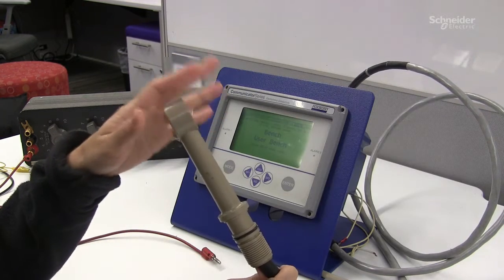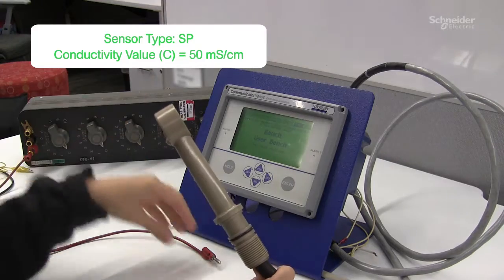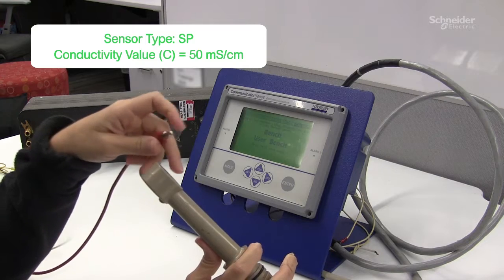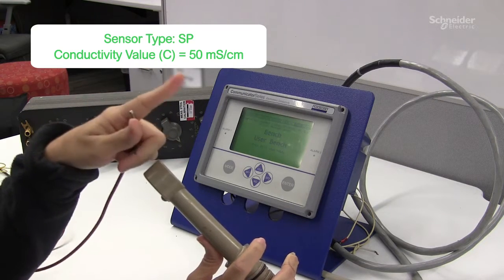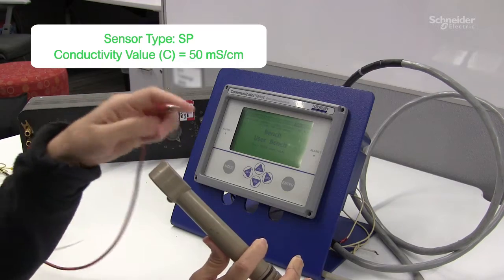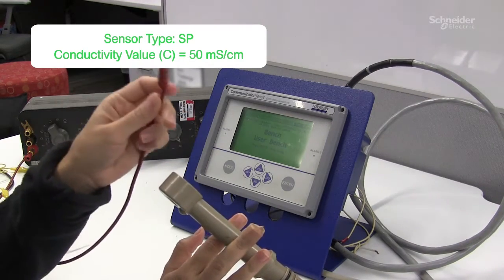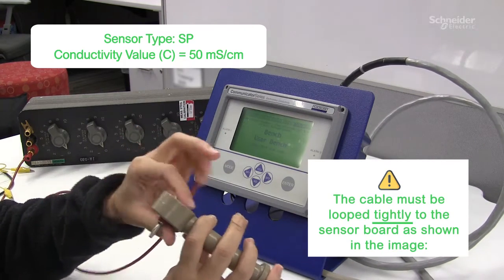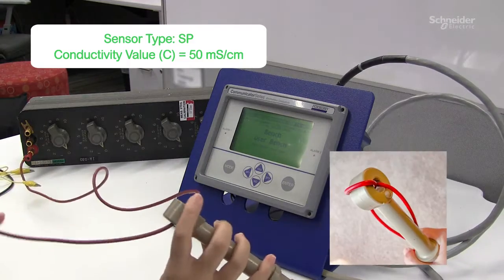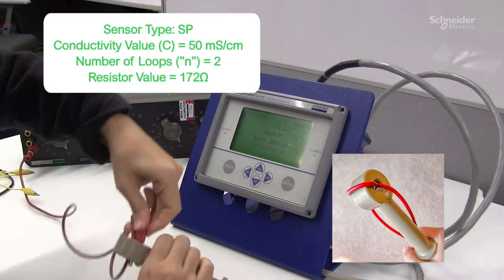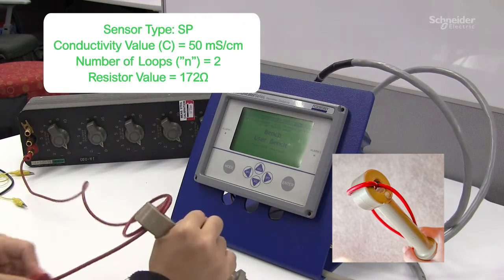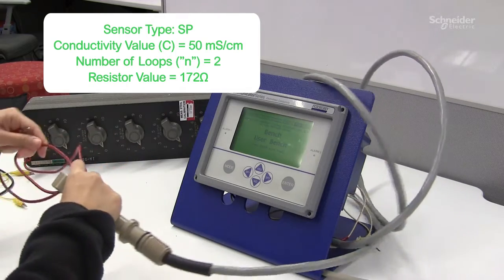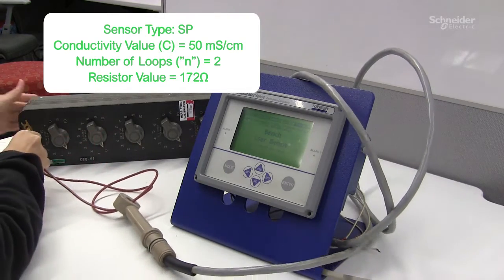And if I wanted to have 50 millisiemens with just one loop in the board, I will get a resistivity that is below 100 and that is not recommended. So when that happens, like in our case, you need to loop more loops of wire through the sensor board. And according to our calculations, if I were to do two loops of wire through the board, I'm going to connect this back to the decade box.